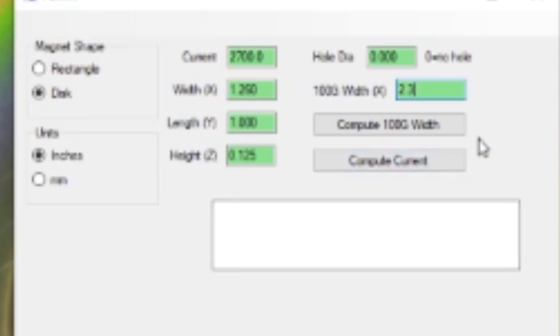There's no hole and the width at the 100 gauss length was 2.3 inches. So with this tool we can say compute the current of the magnet so that we have the magnet listed in our table of 2,700. Based on the 100 gauss location, this computes it at 2,100 amps.